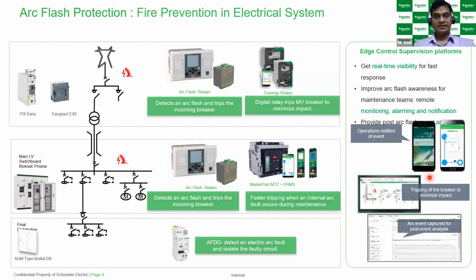And the second most common device, like the Easergy relay, is also a communicable device. The same parameters work, but the difference between the arc fault relay and the Easergy relay is that if you have a complex system, and if you are designing big hospitals, where you want dedicated protection in every device, you need to mount this Easergy relay. So if any arc arises and affects the system, it automatically trips the circuit breaker within a second, within 40 milliseconds, and the complete system will switch off and protect the system.